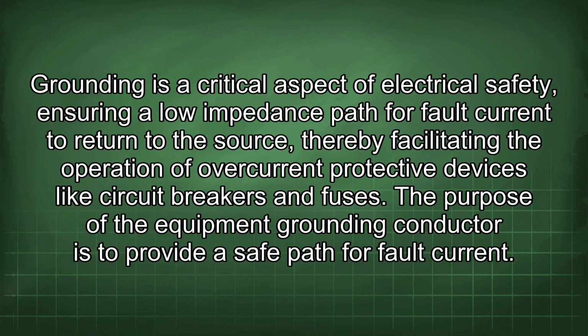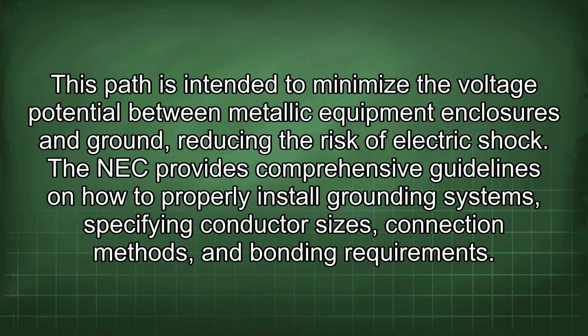Grounding is a critical aspect of electrical safety, ensuring a low impedance path for fault current to return to the source, thereby facilitating the operation of overcurrent protective devices like circuit breakers and fuses. The purpose of the equipment grounding conductor is to provide a safe path for fault current. This path is intended to minimize the voltage potential between metallic equipment enclosures and ground, reducing the risk of electric shock.